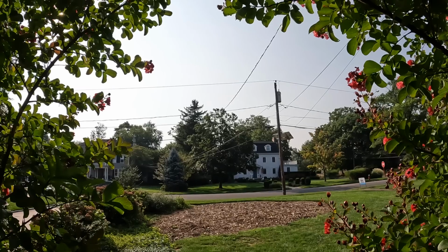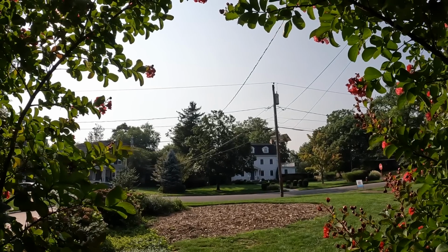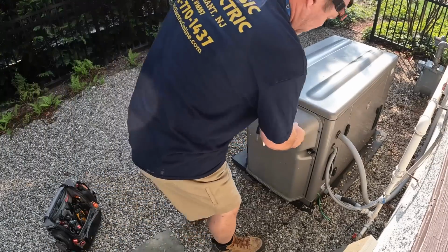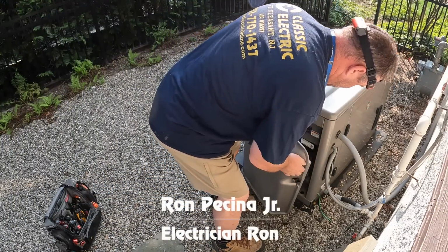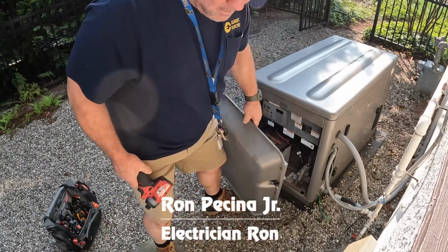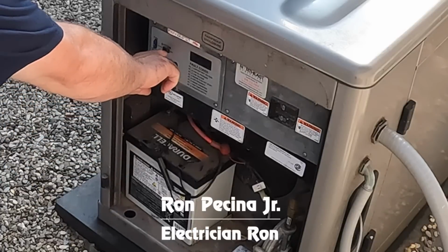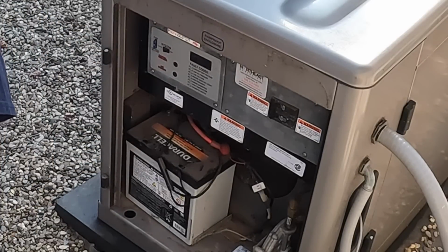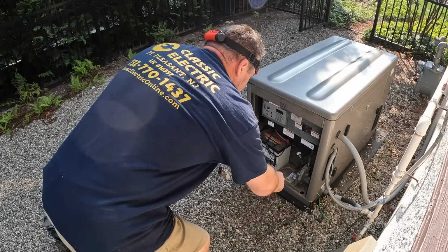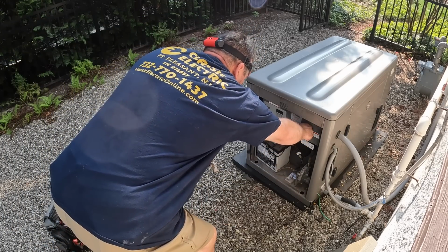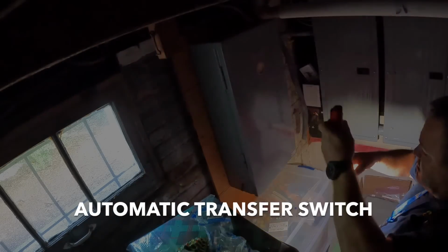Power has been off for a little while, so the generator's been running. But before I work in that transfer switch, I have to turn the generator off because I don't want to get shocked. So I turned off the generator, and as a precaution, I also turned off the circuit breaker, so there's no possibility of getting shocked or any live wires as I start connecting the new feeder cable to this automatic transfer switch.